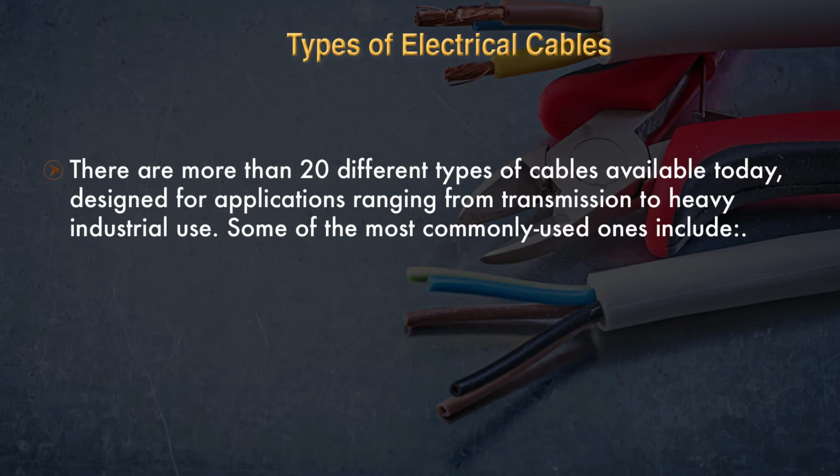And what are those requirements? First one is, the conductor used in a cable should be tinned, stranded copper or aluminum of high conductivity. Stranding is done so that the conductor becomes flexible and carries more current. Second requirement is that the conductor size should be such that the cable carries the desired load current without overheating and causes voltage drop within a permissible limit.